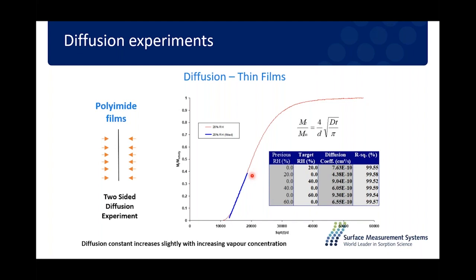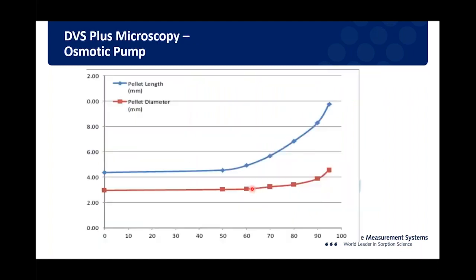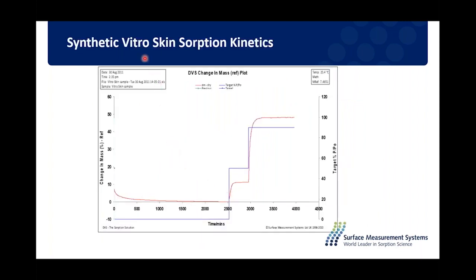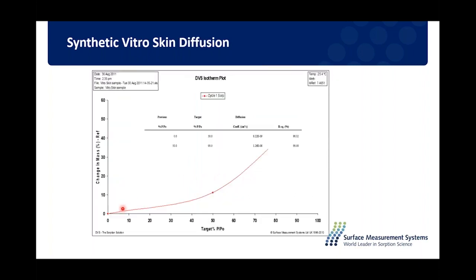DVS can be used with a wide range of geometries looking at not just uptake but also kinetics — how quickly or slowly something goes in and out of a material. For example, using a thin film of synthetic skin called vitro skin, we can make step changes in relative humidity and measure how quickly water goes in and out of those samples with different surface treatments. From this we can get the diffusion coefficient at each step change in relative humidity with different coatings, humectants, oils or creams, to look at skin transport properties as a function of RH.